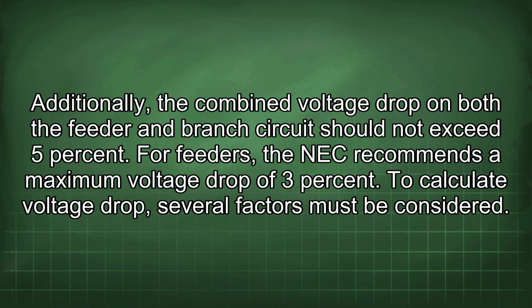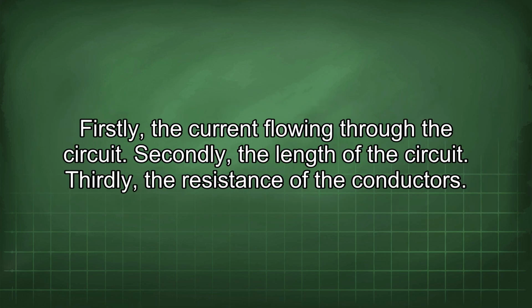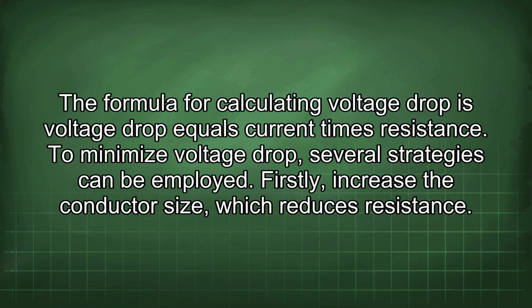To calculate voltage drop, several factors must be considered. Firstly, the current flowing through the circuit. Secondly, the length of the circuit. Thirdly, the resistance of the conductors. The formula for calculating voltage drop is voltage drop equals current times resistance.